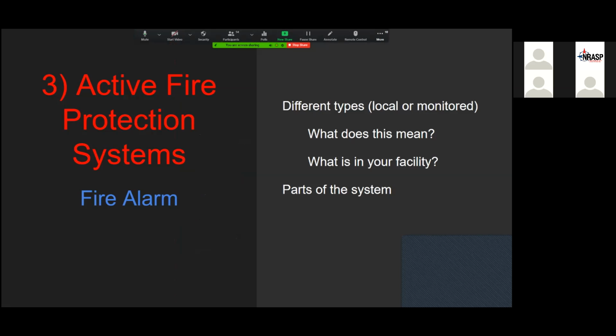Let's talk about fire alarm systems, another part of the active fire protection system. It's designed to recognize there is a fire and notify occupants of the fire, allowing them time to evacuate. Some fire alarm systems are monitored by a monitoring company, which will contact the local fire department in the event of a fire alarm activation, and some systems report only locally. Now, it's very important that you know what type of fire alarm system you have in your building. Because if you have a fire alarm system that responds and reports locally only, it's not telling the fire department there's a fire. So we need someone in your facility to actually make that phone call to 911 to let us know that the fire alarms are activated and there's something that needs to be investigated.